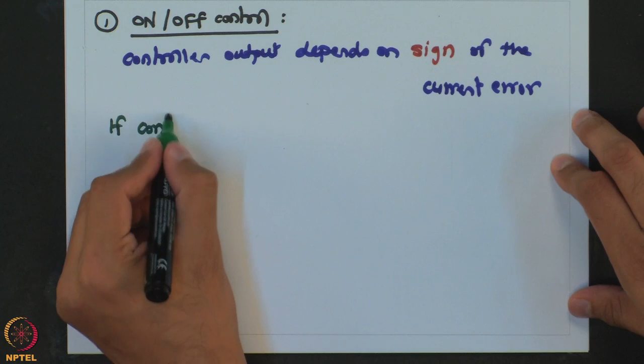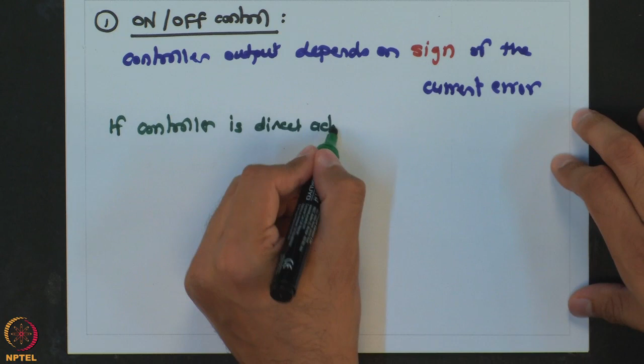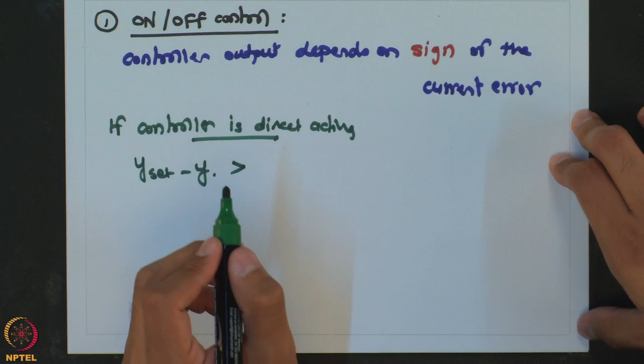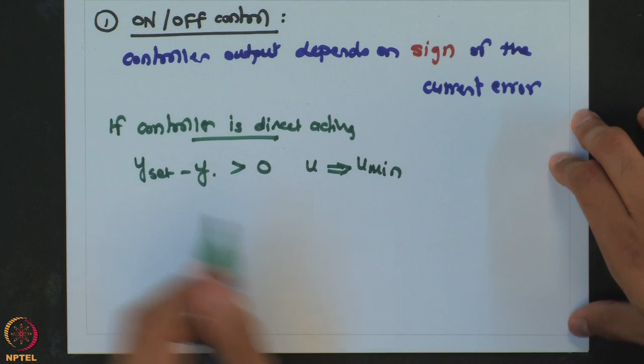So, let us say if the controller is direct acting, and if y set minus y, which is the error, is greater than 0, then u will be equal to the minimum value of u. If y set minus y is less than 0, if the error is negative, then u will be made equal to the maximum value of u. And the exactly opposite pairing works when we have a reverse acting controller.